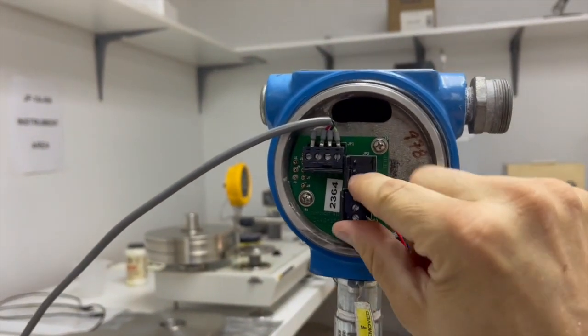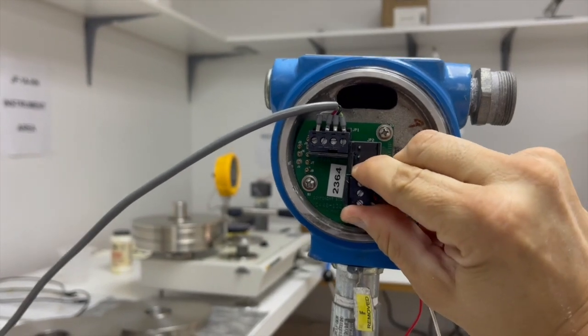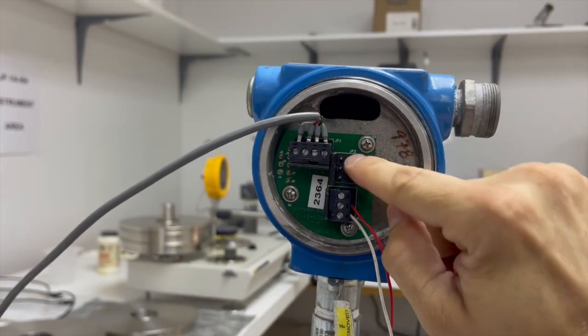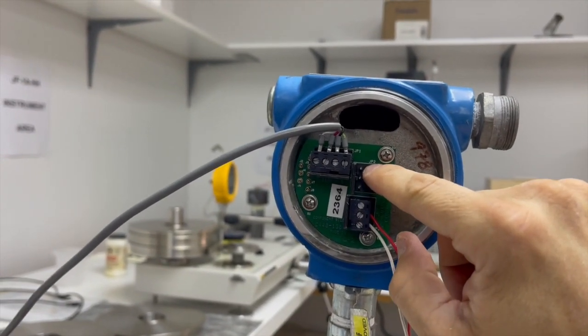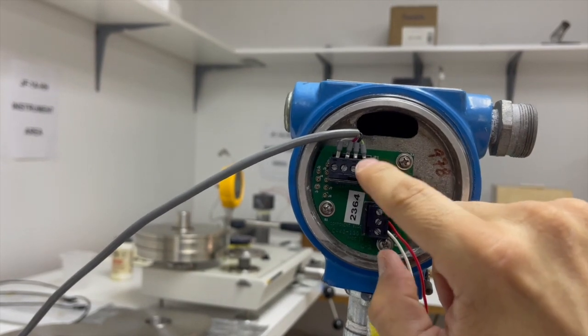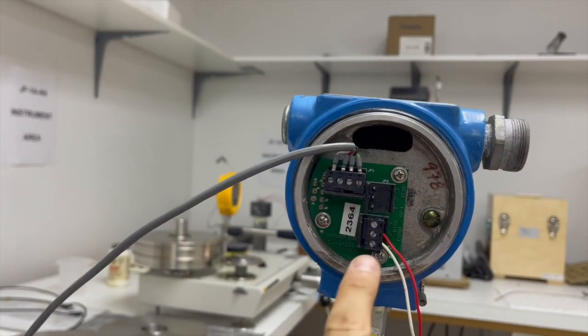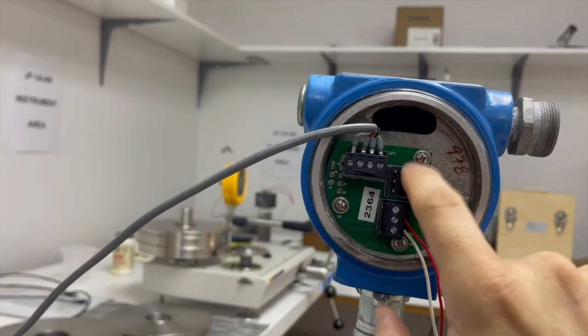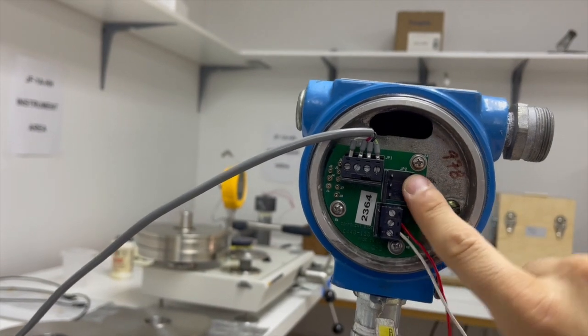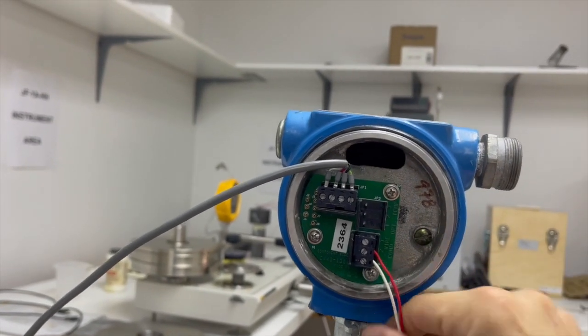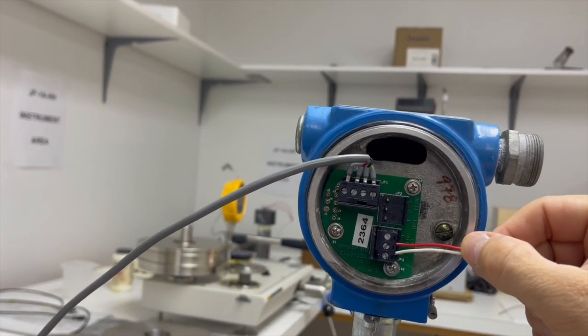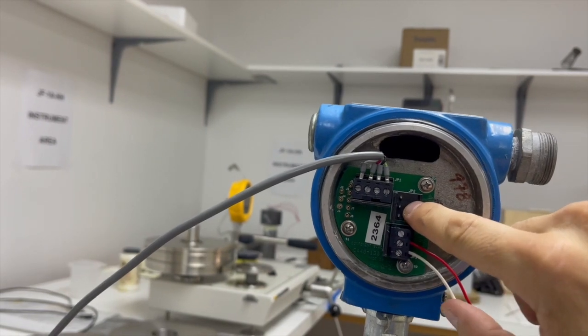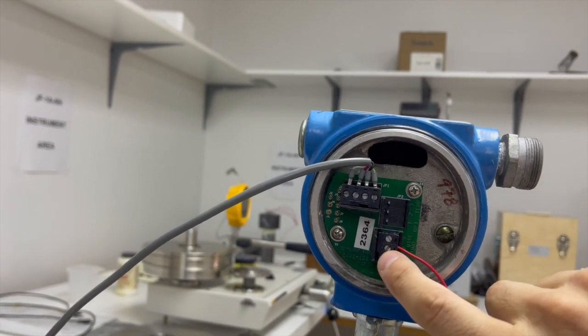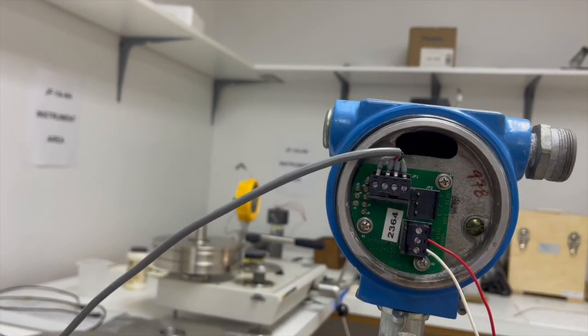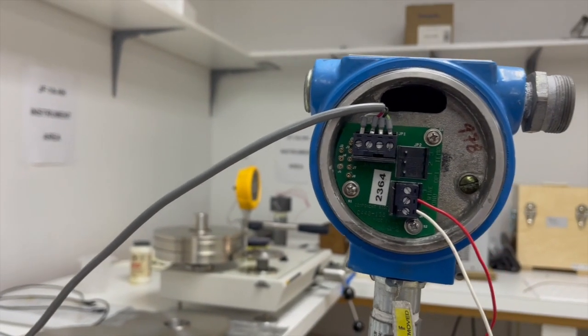So to do that, you would disconnect power from the conductivity loop, put on the temperature loop, and you also need power either running through the serial port or through the conductivity port to have the instrument on while doing temperature. Conductivity can be powered just by the conductivity loop. The temperature loop needs power coming from either conductivity or from the serial port. So just keep that in mind.